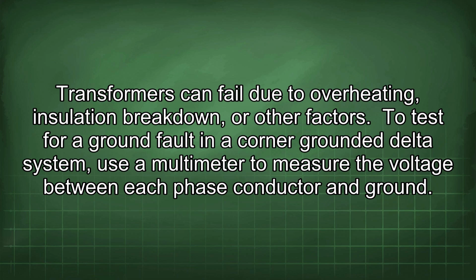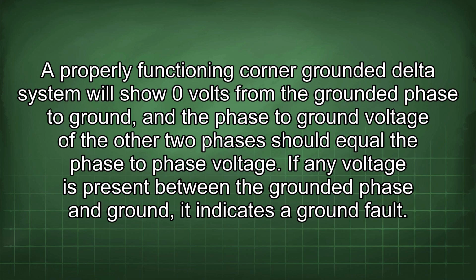To test for a ground fault in a corner-grounded delta system, use a multimeter to measure the voltage between each phase conductor and ground. A properly functioning corner-grounded delta system will show 0 volts from the grounded phase to ground, and the phase-to-ground voltage of the other two phases should equal the phase-to-phase voltage. If any voltage is present between the grounded phase and ground, it indicates a ground fault.